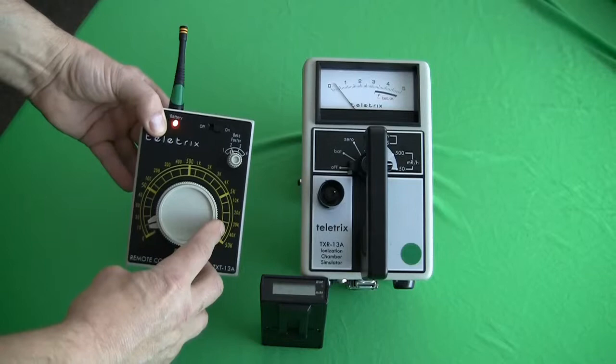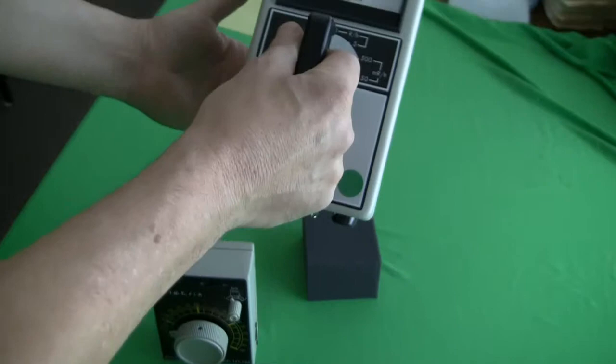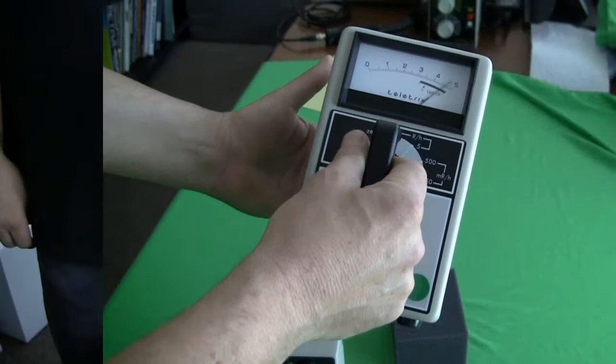We have the ability to set a beta factor. In this case, it's set to 2. When the window is open, the reading increases by a factor of 2. When it closes, the reading decreases to its original setting, as it existed on the remote controller.